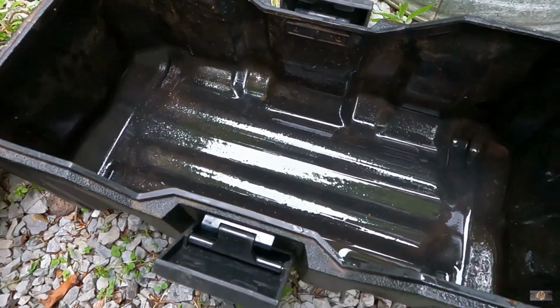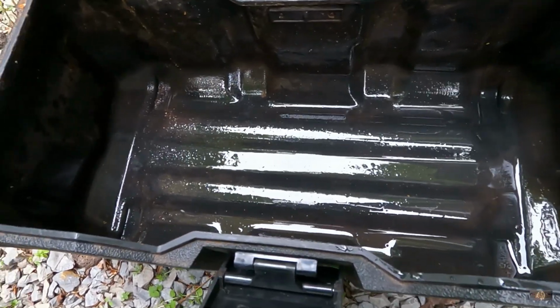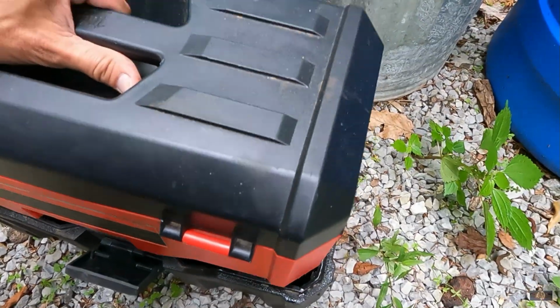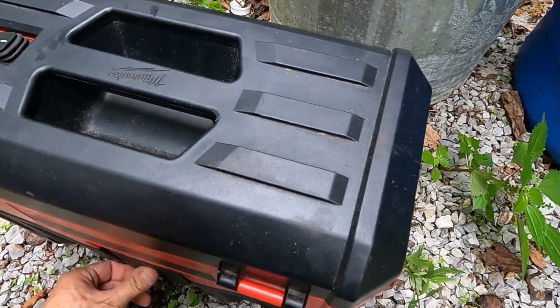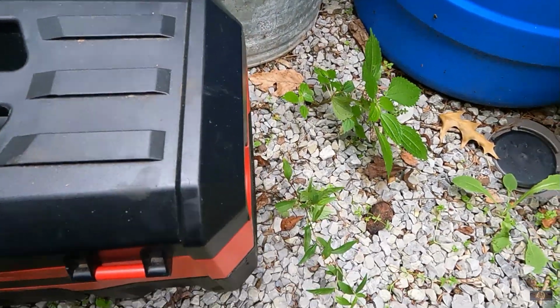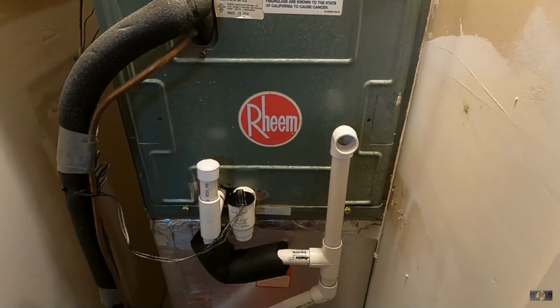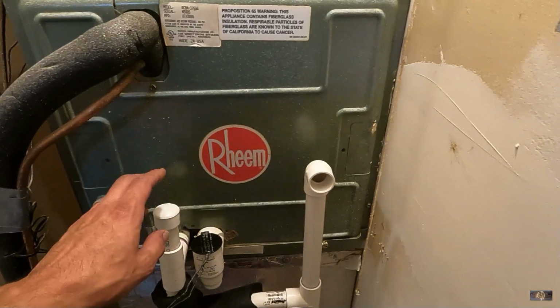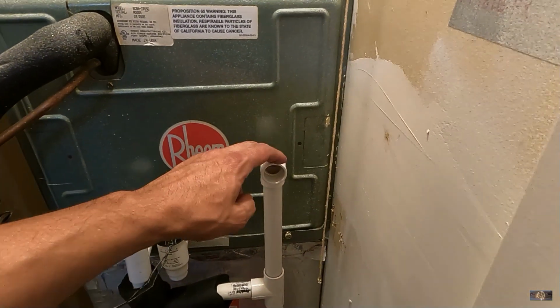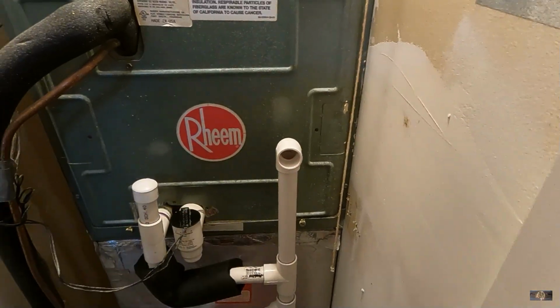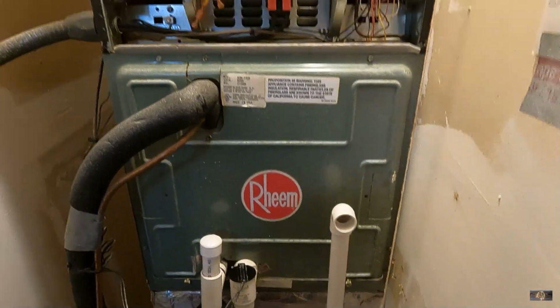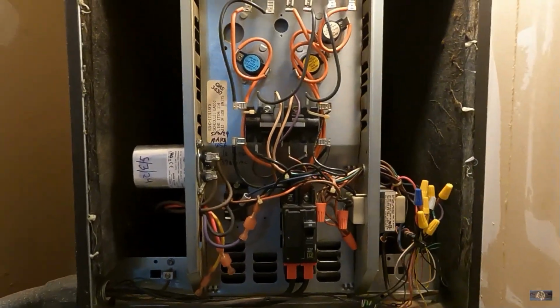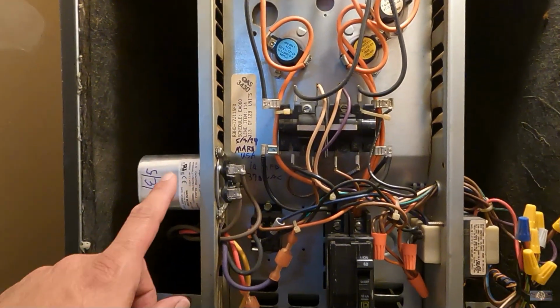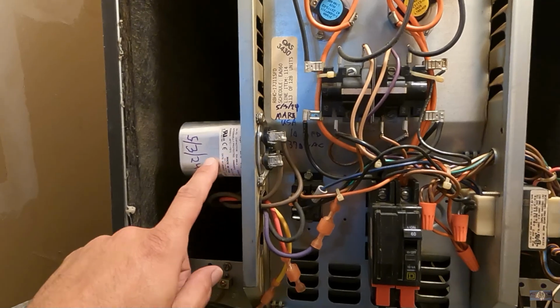So now we're going to prime that trap, check the capacitor, wipe down that indoor unit, and test out this machine and make sure that it's running properly. Okay, I got my drain back together, put my 90 back on, took the cap off of it, threw the cap back in my bag, and went ahead and checked the electrical connections out in here. Everything looked okay. Looks like I replaced the blower run capacitor.